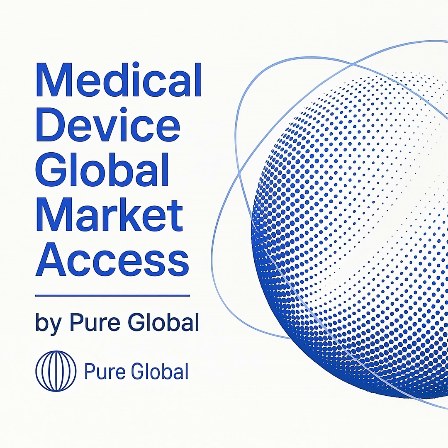A formal UK declaration of conformity must be drawn up, and once complete, the UKCA mark can be affixed to the device. When the UKCA mark is used, the name and address of the UK responsible person must also be included on the product labeling, its outer packaging, or in the instructions for use. It is important to note that these rules apply to Great Britain only. Northern Ireland continues to follow EU regulations, requiring a CE mark.